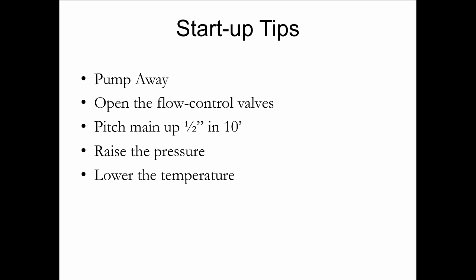This was taught to me by an old time oil heat service manager on Long Island that was working in an area where they had a lot of these systems and they went into service and they just drained the system and had to get it going again right away. And so they worked with Henry's law that says gases dissolve in liquid in proportion to pressure and temperature. So this fellow Howie who was the service manager said to me they'll go in there and lower the temperature because when water gets cooler it tends to absorb more air and then they would raise the pressure almost up to 30 psi because as you raise the pressure the water will absorb more air. And by doing that that's often enough to give them a kickstart to get the thing going.